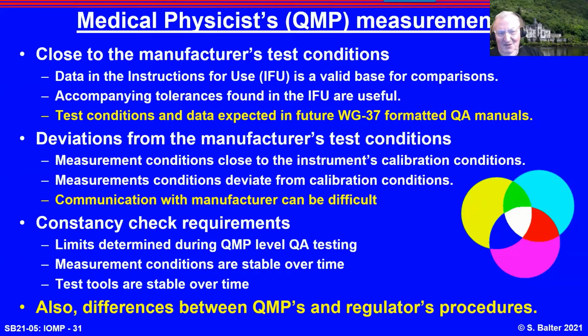Yes, it passes, no, it fails, because different people are using different instruments and different processes and different standards. Once you've done that, constancy checks should be done. You set up the limits during the physics level testing. You need stable measurement conditions and you need stable test tools. And again, mismatches between the regulators' processes and instruments and the clinical physics are not uncommon. So these have to be factored in as well.